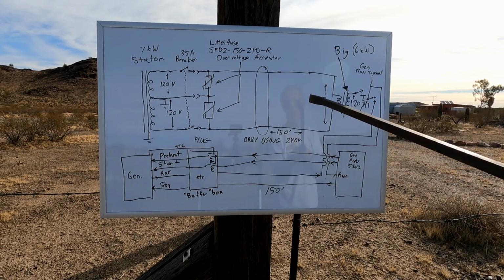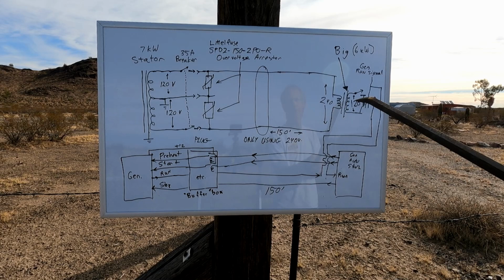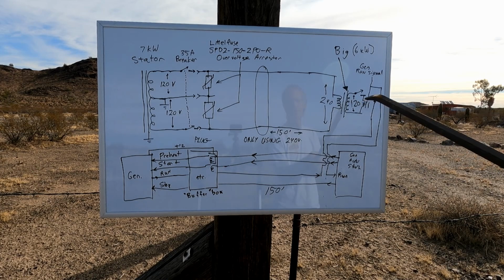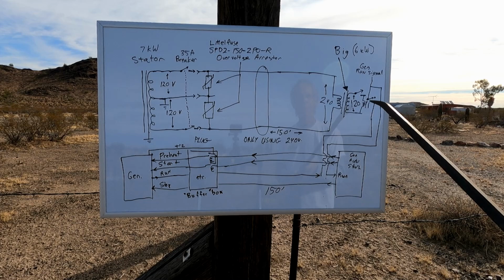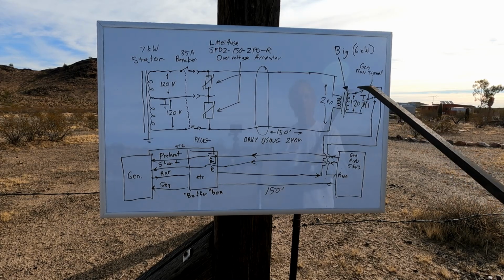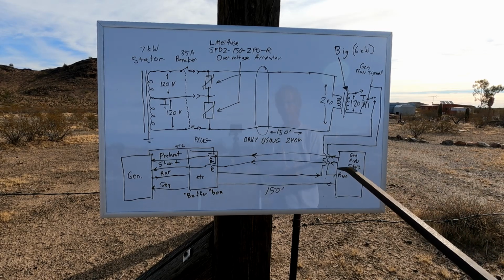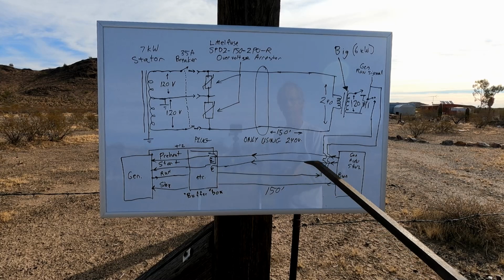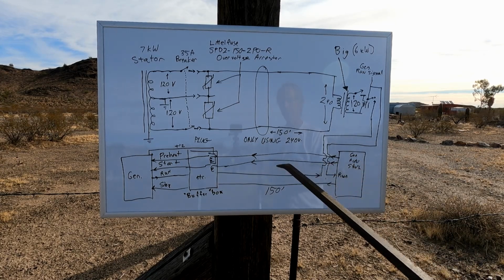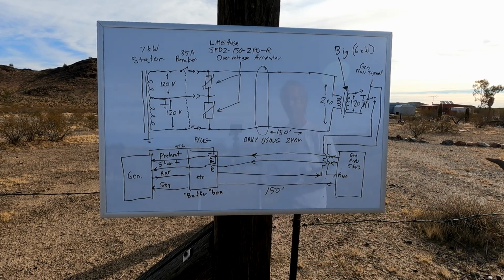In my case, I'm only using 240. At the far end, I have a transformer that converts everything back to 120, because everything in my place is 120. I have no use for 240. So the other thing to bring up here is how this is related to and ties into the generator auto start, because after the breaker on the 120 volt side at the house, I have a little relay. Now when we look at generator auto starts, the setup like I've got has a signal for preheat for the diesel generator that runs for a few seconds. Then it has the start command that does like 3 starts, and if the 3 starts don't catch it, it faults out.